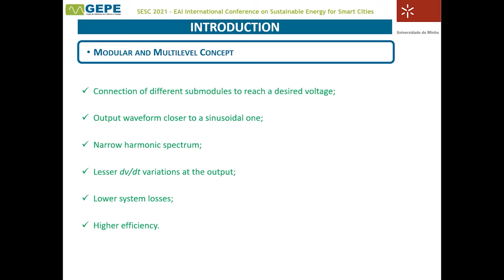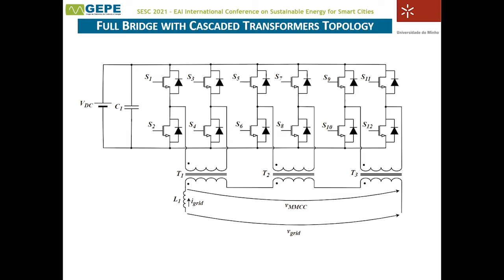As already mentioned, the topology of MMCC used was the full bridge with cascade transformers and a common DC bus, presented in the figure. This converter consists of the parallel association of three full-bridge submodules sharing the same DC bus. The output of each submodule connects to the primary side of a power transformer, while the secondary side is connected in series with adjacent transformers. In this study, these power transformers have a transformation ratio of 1:1 and are used to create the multilevel feature since there is only one DC bus.